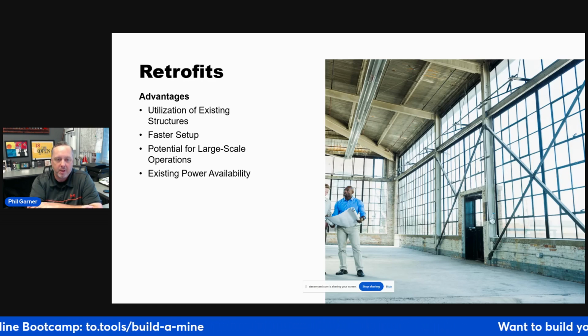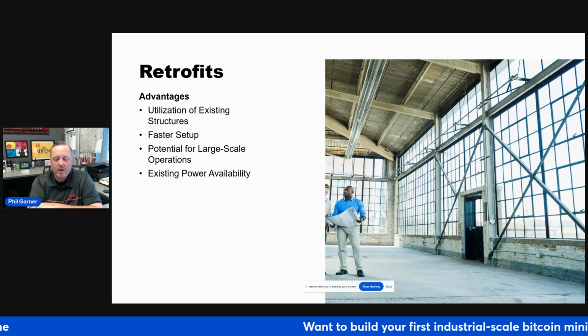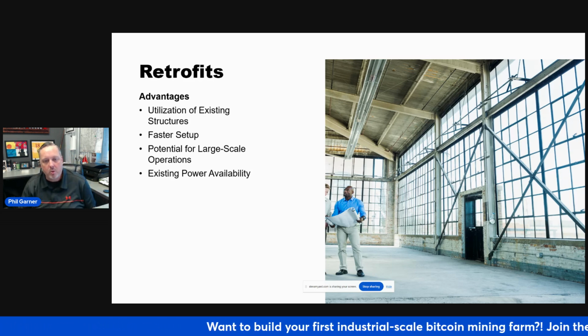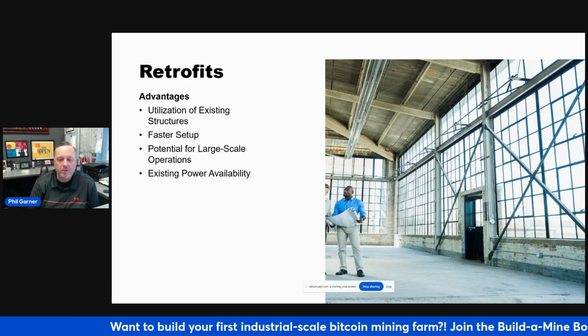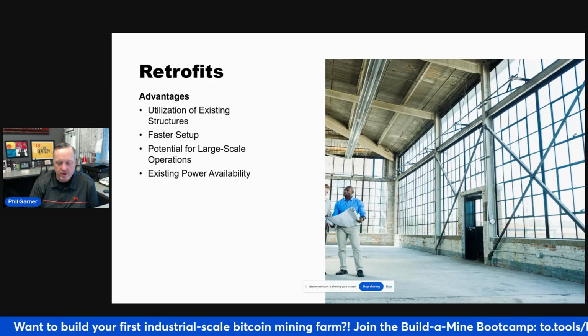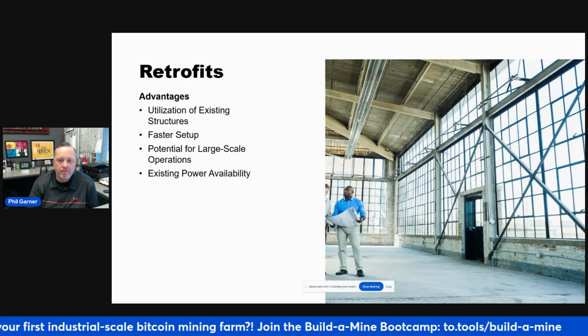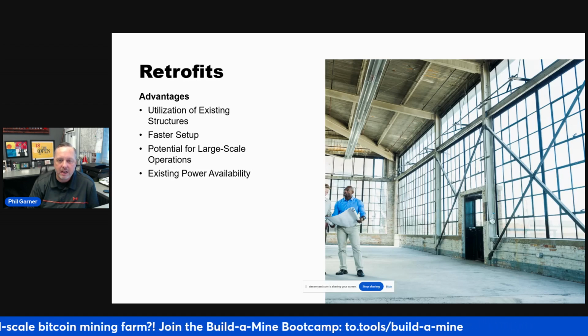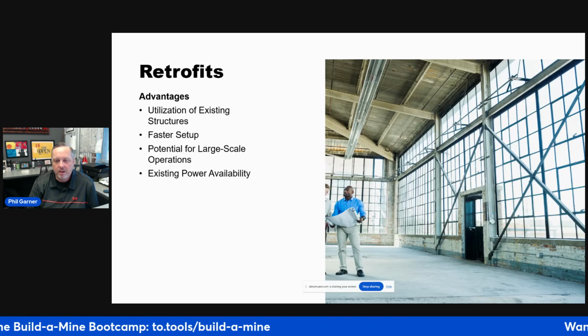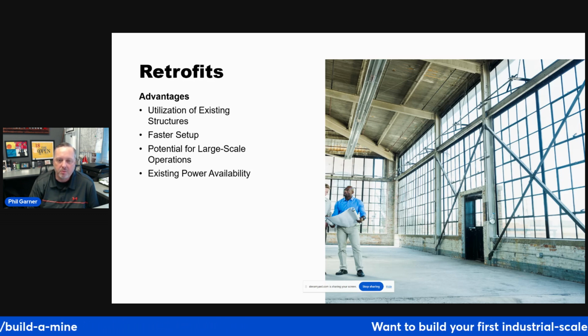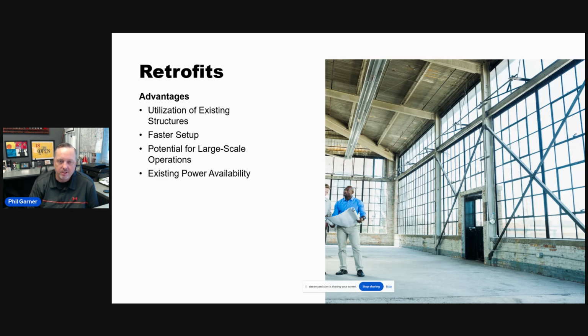This is probably one of the biggest advantages. If you already have a 20 or 50 megawatt facility and you're now looking to scale up to 250 or 300, right now you're probably 2 to 3 years out by the time you found the land, made an agreement with a utility company, got a substation built, got the design done, got built, and you're in.